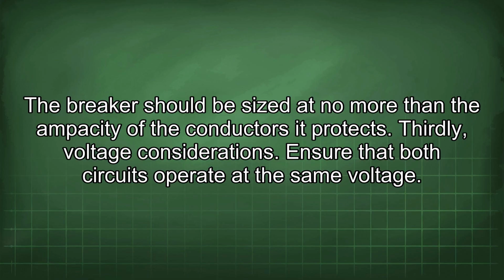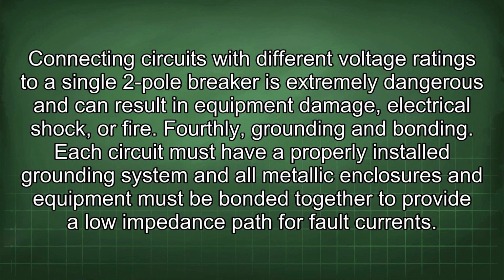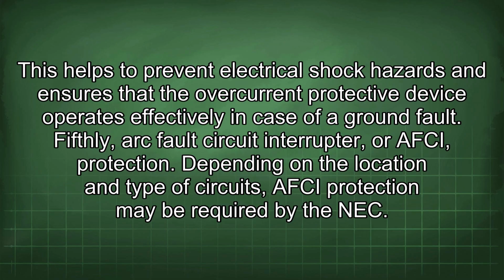Thirdly, voltage considerations. Ensure that both circuits operate at the same voltage. Connecting circuits with different voltage ratings to a single two-pole breaker is extremely dangerous and can result in equipment damage, electrical shock, or fire. Fourthly, grounding and bonding. Each circuit must have a properly installed grounding system, and all metallic enclosures and equipment must be bonded together to provide a low impedance path for fault currents. This helps to prevent electrical shock hazards and ensures that the overcurrent protective device operates effectively in case of a ground fault.